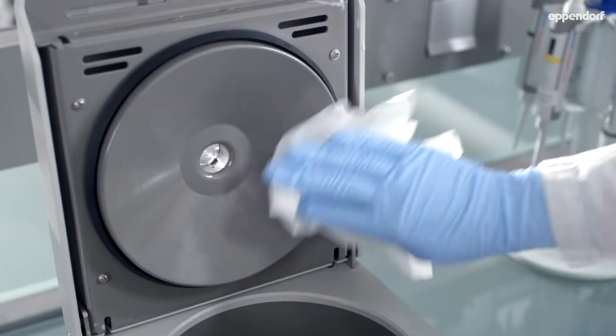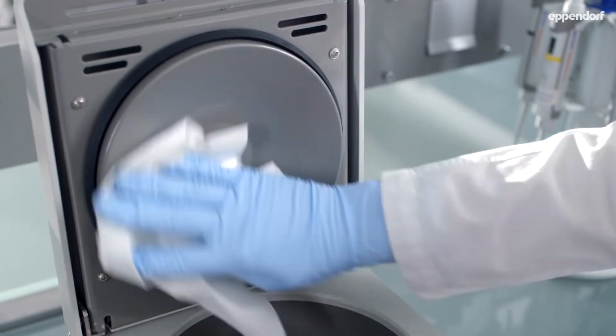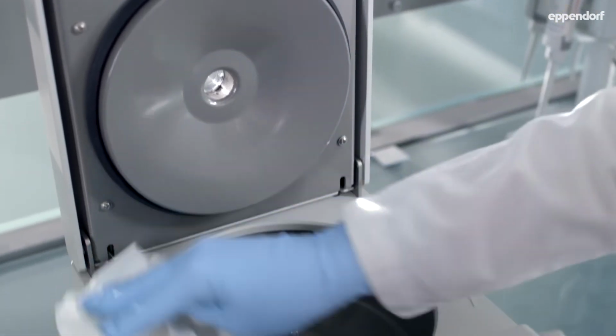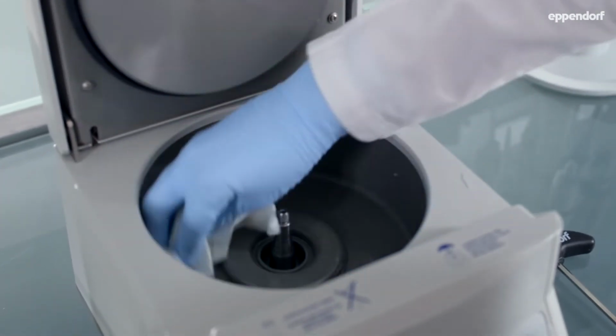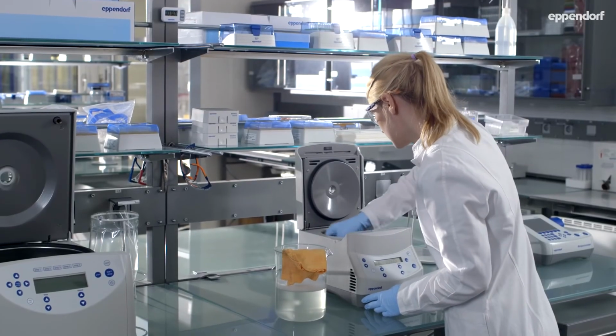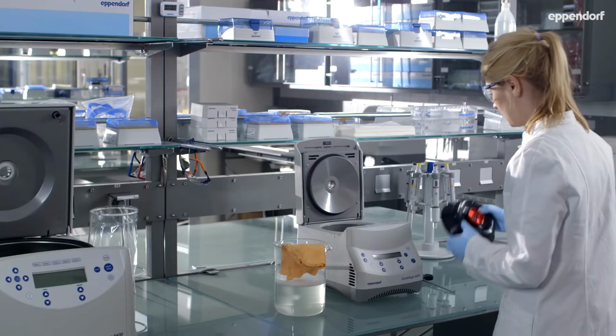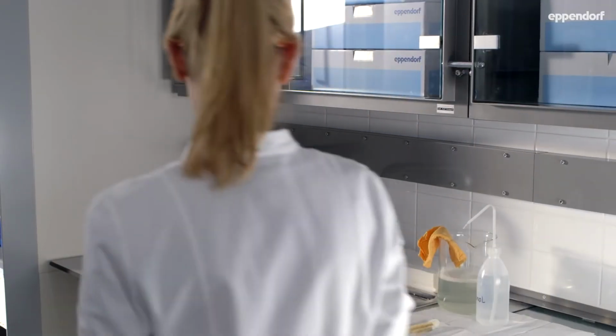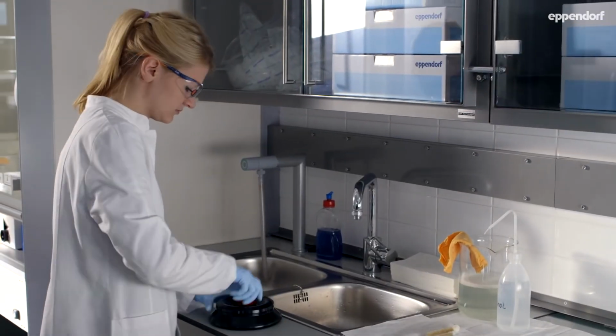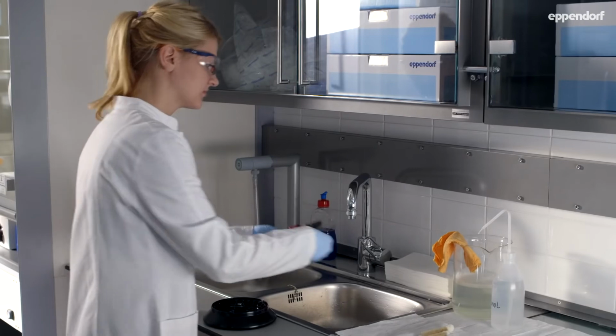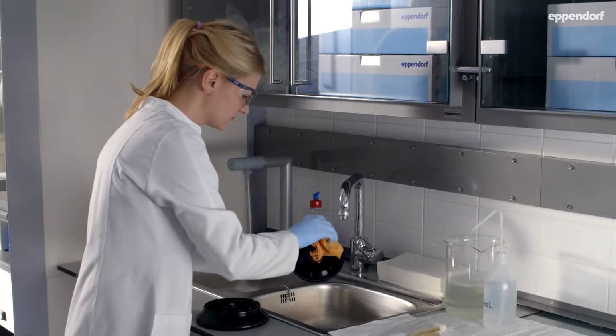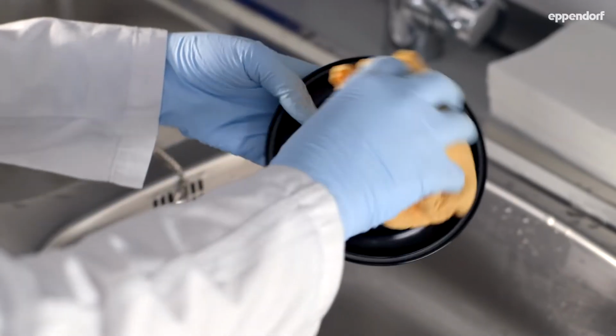In particular, if salt incrustations or contamination with other aggressive chemicals are detected, any residue should be wiped off to extend the life of your device. Do so with the centrifuge rotors as well, to completely remove salt and chemicals which may support the formation of corrosion.